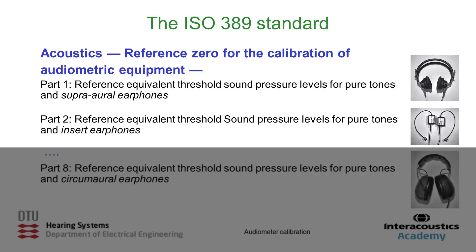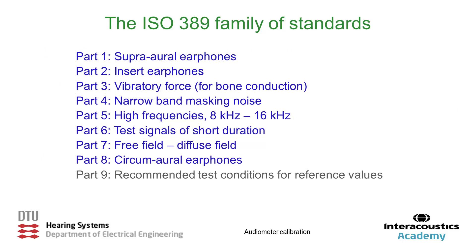Part two of the standard has the same main title but covers insert earphones rather than supraaural earphones — earphones that go into the ear canal. Part three covers vibratory force levels, which is for bone conduction — calibration of the bone vibrator.